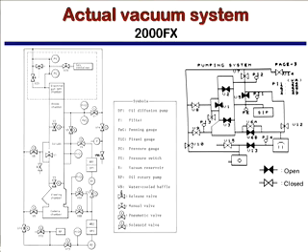You put the thing back, and you'll recall it took just a minute or two, right? Because it was actually already in pretty good vacuum. It hadn't evacuated yet. And then, first it checked with the roughing pump, and then it checked with valve 6A, right? And then 6B. You might even remember we watched that sequence go through. Okay? So I will probably do that in lab for everyone. Initially, do that in the way that you start to see some of these things move around.